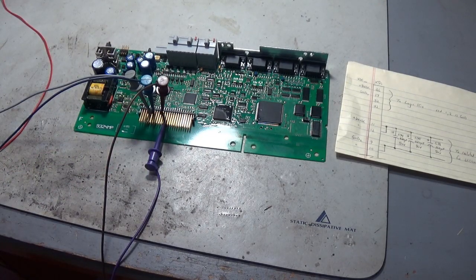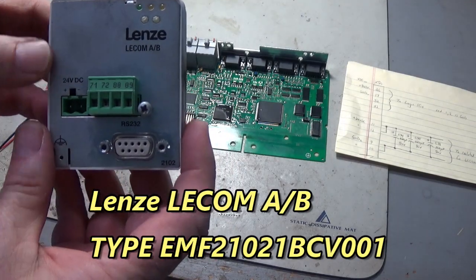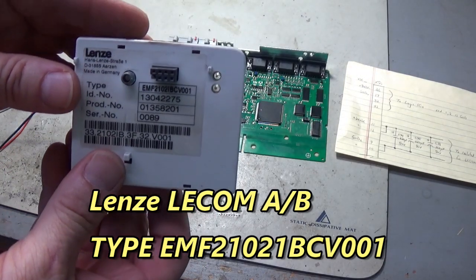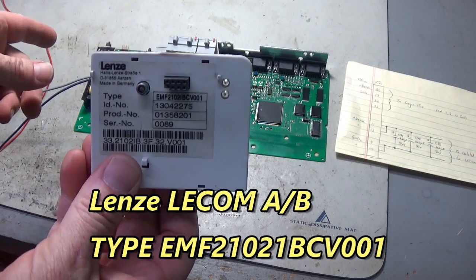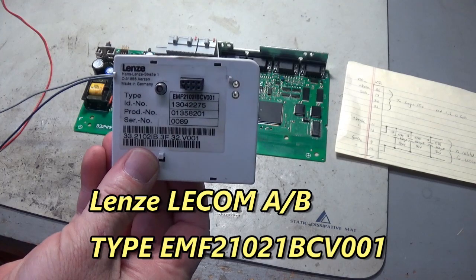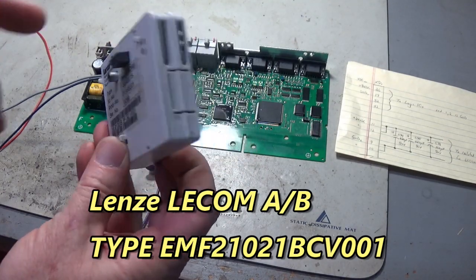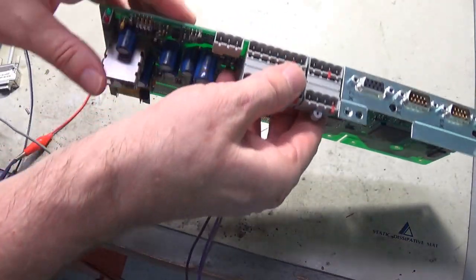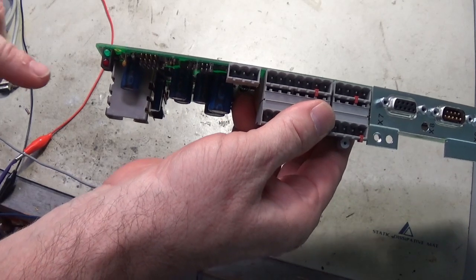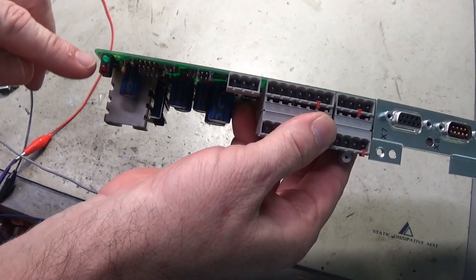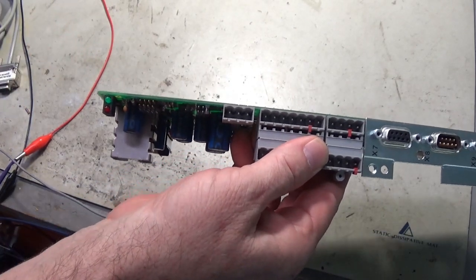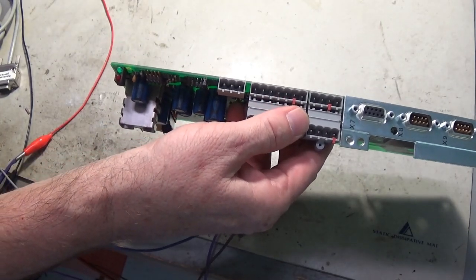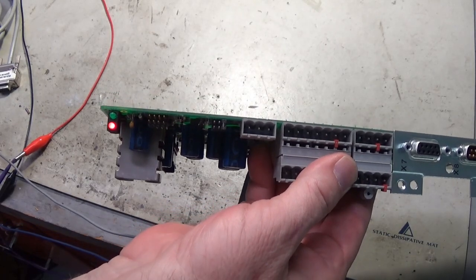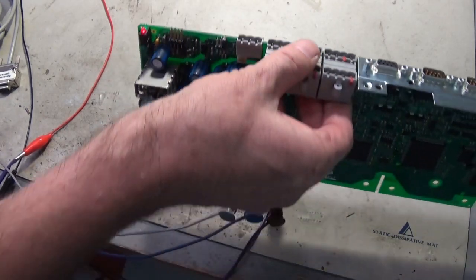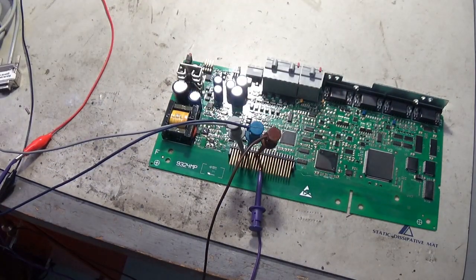Power supply wise, we need to hook up the LECOM. Flip that around so you see that part number. You need this to connect your control board to the laptop. Now, if we're hooked up correctly, and I double checked, we are. When I power this up, that red and green LED will come on, then the green LED will go off and the red LED will start blinking. There we go. Okay. Turn that off.